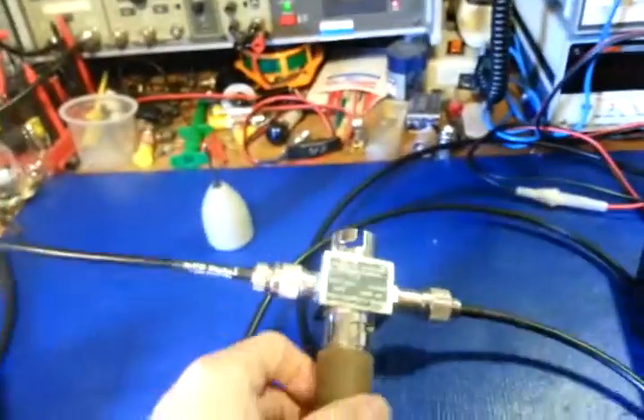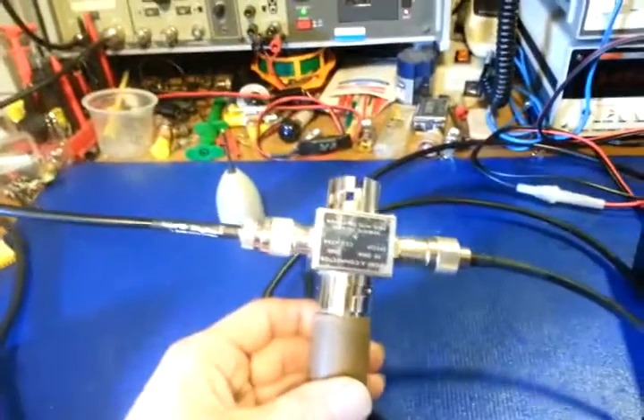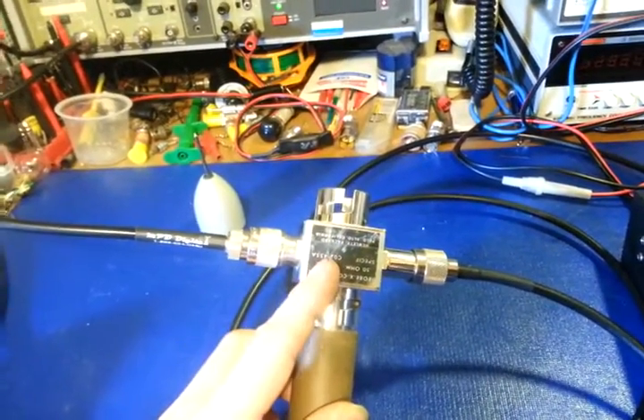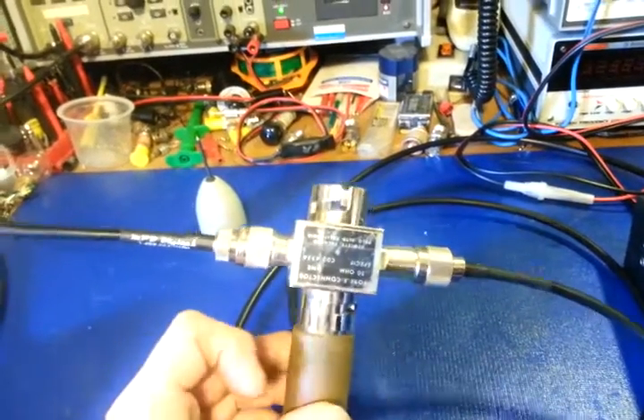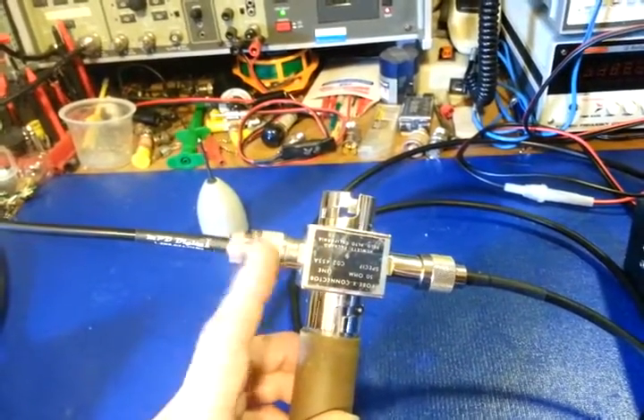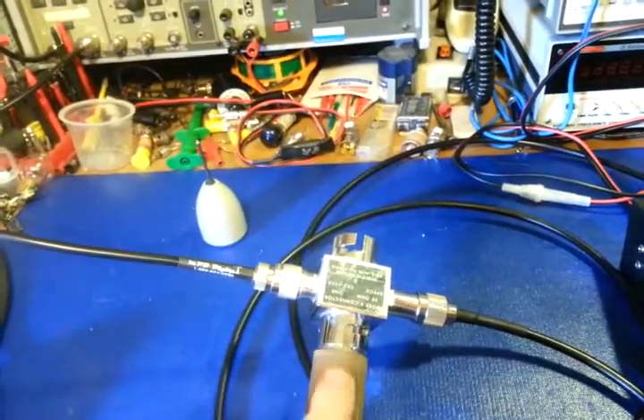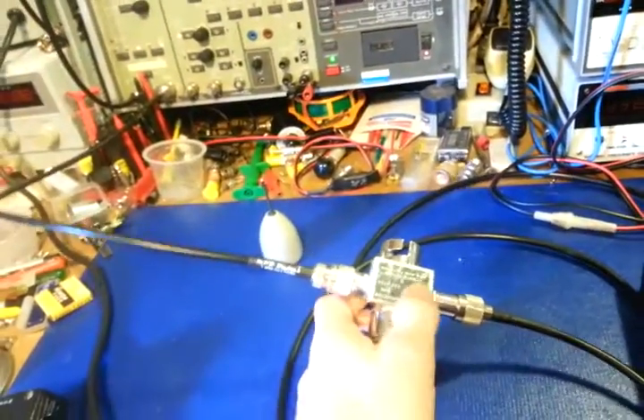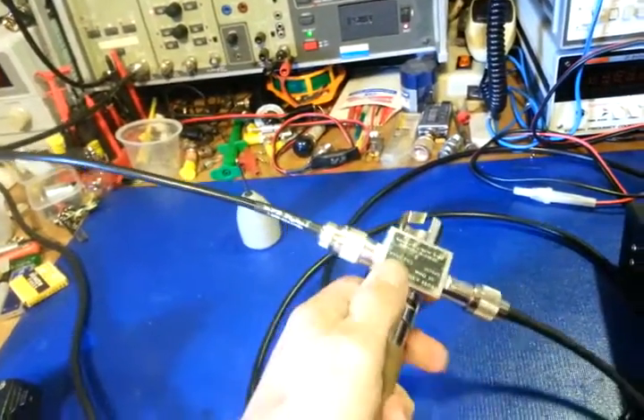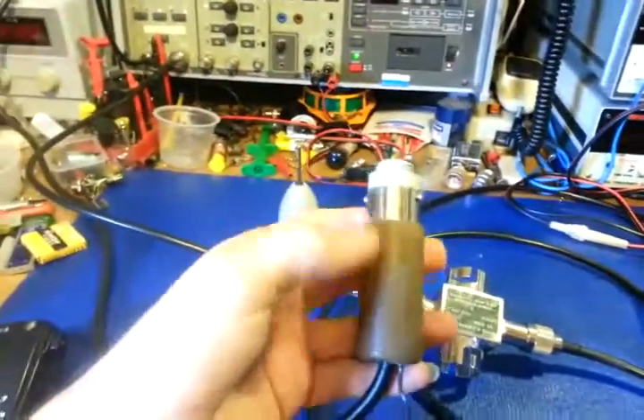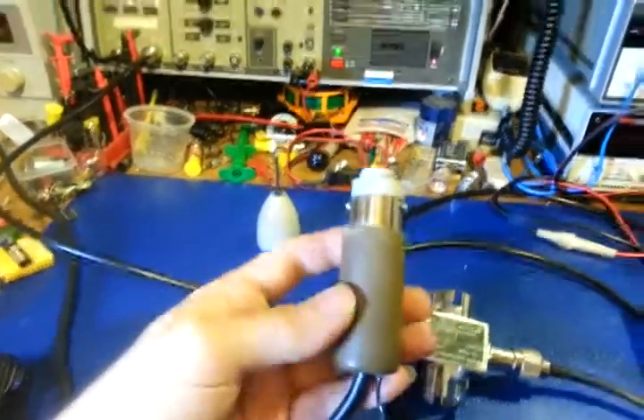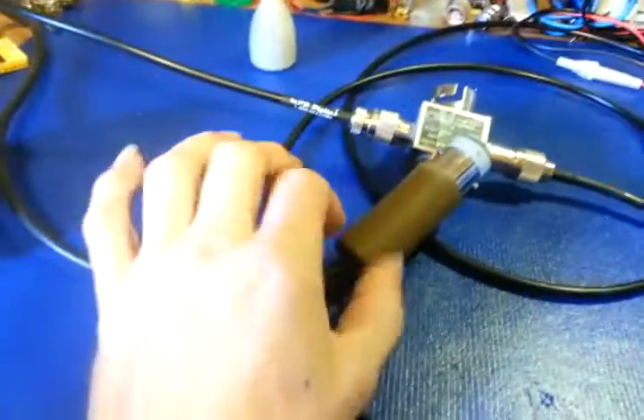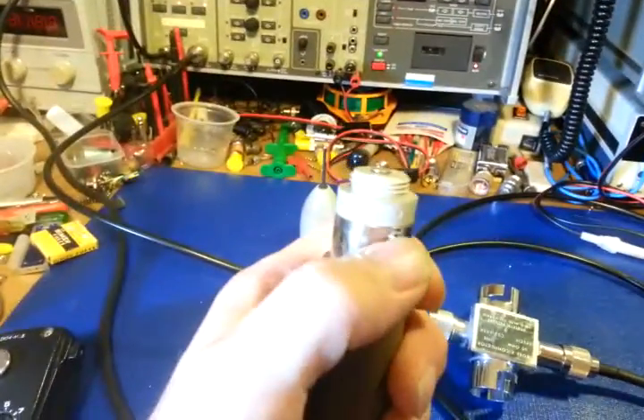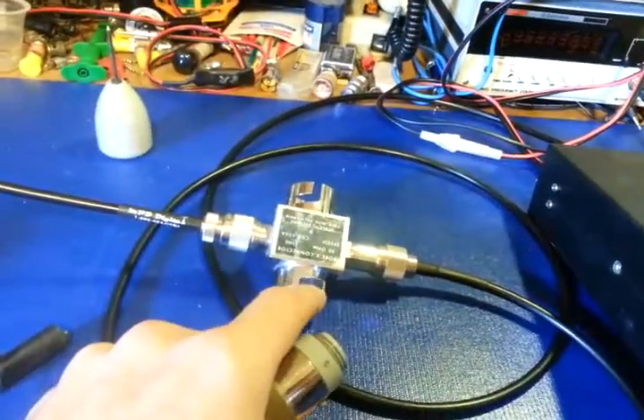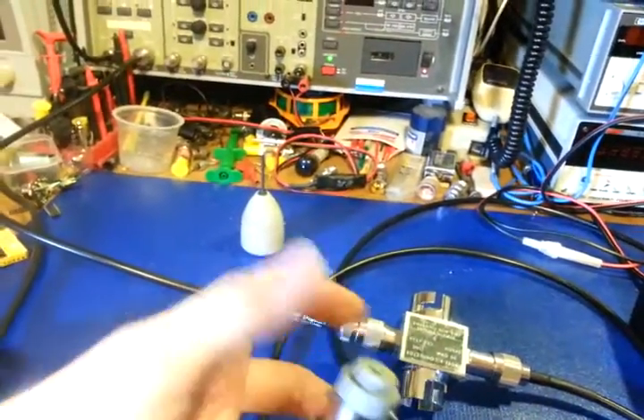Now, the only thing is, and I'll say this mainly for you, buddy, I'm not 100% sure if this probe adapter will work with the probe that you have. I know this will work with the 410B and the 410C, but your probe is a little bit different. Where this one, get it unhooked here, where yours, for starters, doesn't have this rubber insulator to keep your hand from getting hot, but yours has a locking ring on the back you unscrew, and then you pull it out to get to the vacuum tube. This one, you just take these two screws out, which are the ears that lock in on this. You take off those two screws. The cap comes off, and it has a wire.